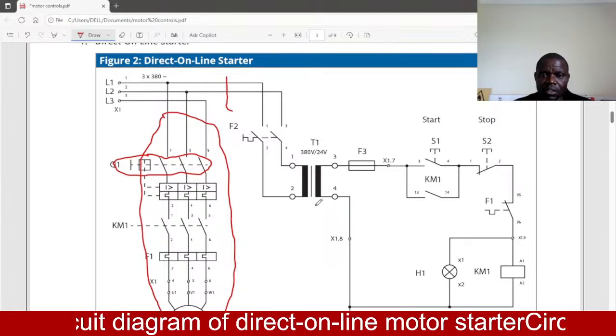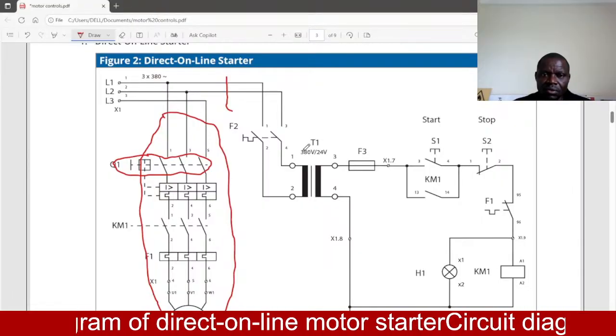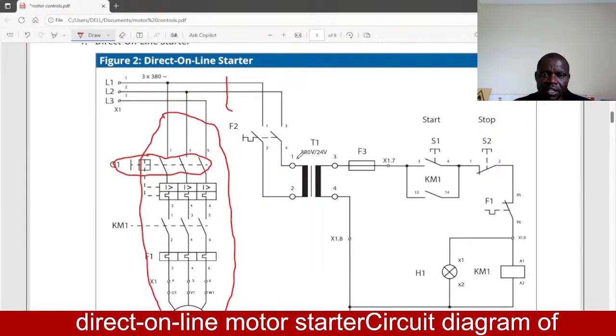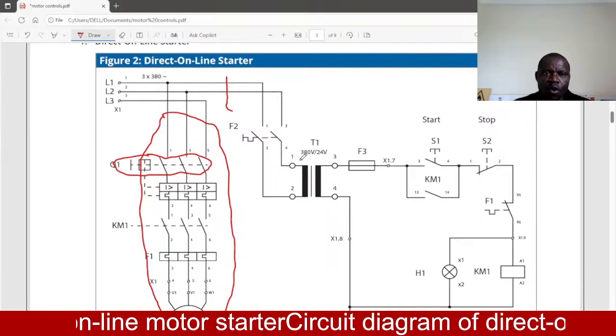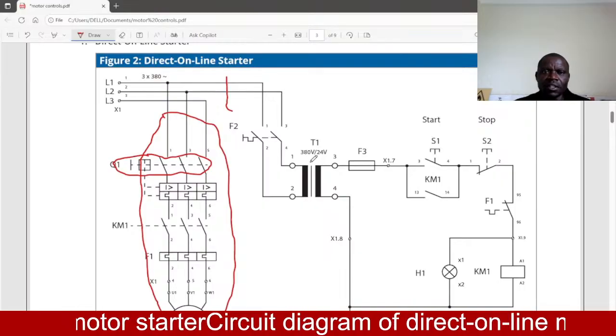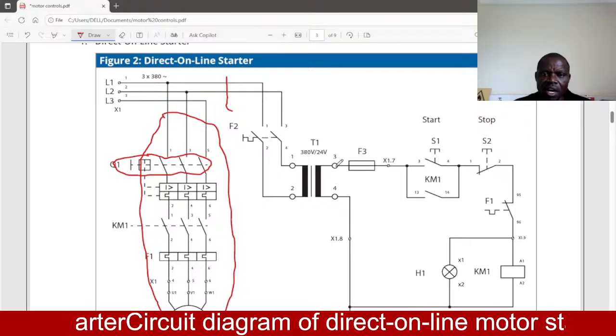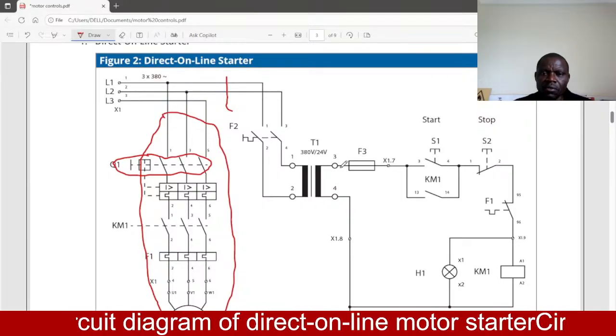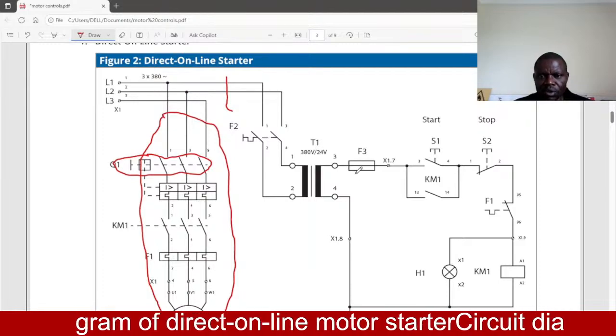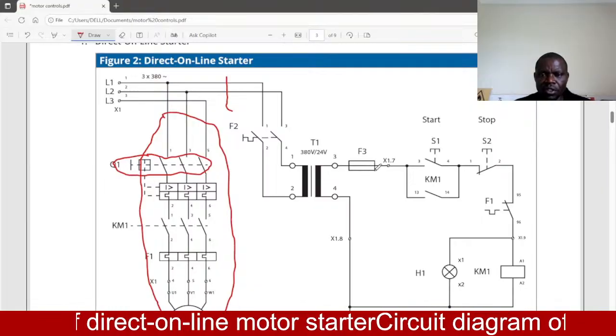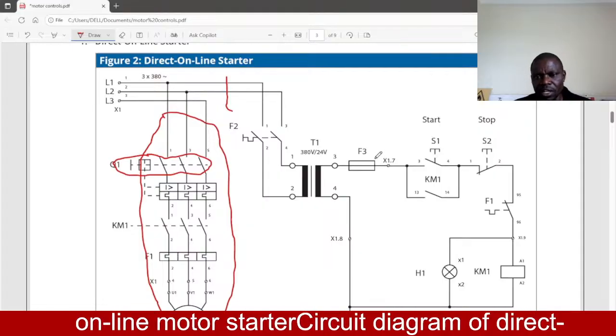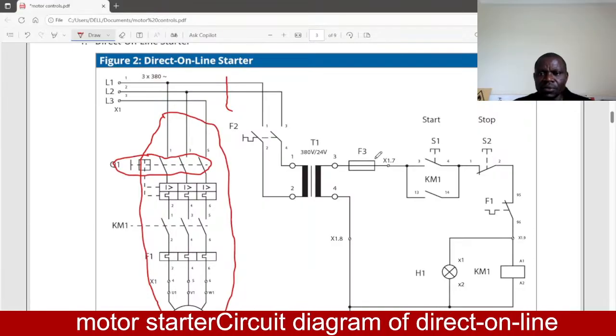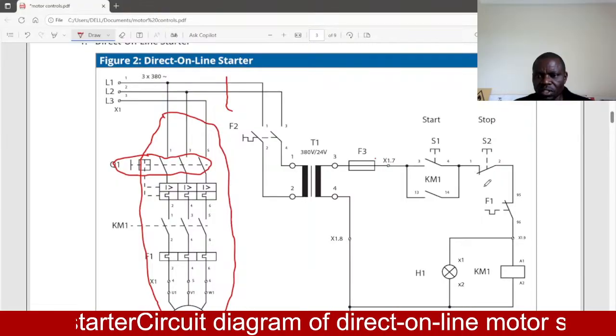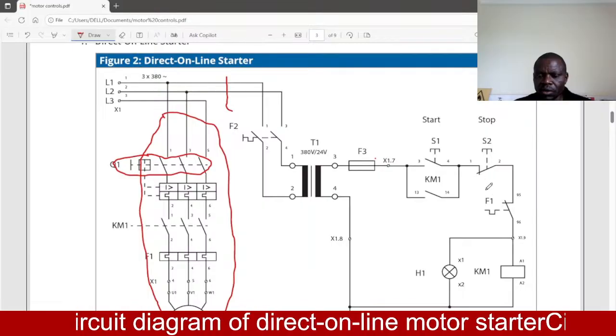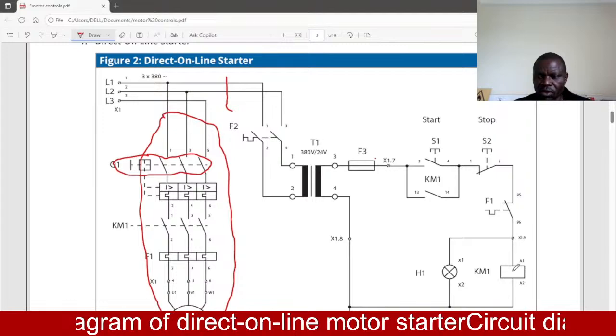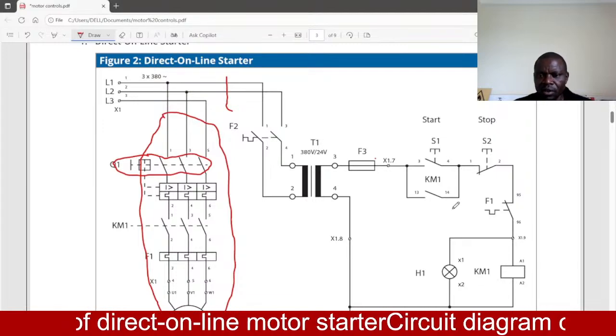Now we have the transformer here. This transformer is rated 380 volts stroke 24. The meaning is that the two lines that feed the transformer are both live, and the live to live gives us 380 volts. Stroke 24 means the output, 3 to 4, is a voltage level of 24 volts. After the transformer, we have the fuse, which is named F3. This fuse can either be a circuit breaker or a fuse; whatever the case, they are all protective devices. It is controlling the circuit conductors of the control circuit here. In case of shorting, that is connecting these circuits without the load, which is our coil here, the fuse or the circuit breaker will operate and will save the situation.